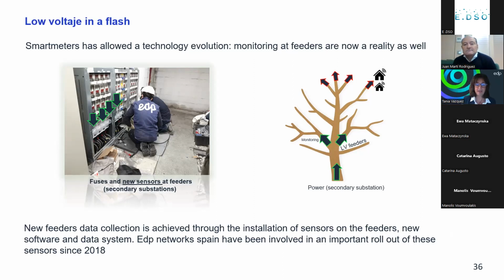EDP Networks Spain has been involved in an important rollout of these sensors since 2018. As you can see again in this tree diagram, we now have monitoring in low voltage feeders. So with smart meters at the customer point and these new sensors, we have a high level of observability or monitoring in the low voltage grid.